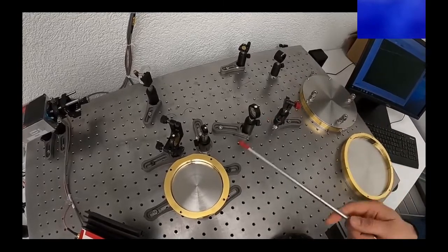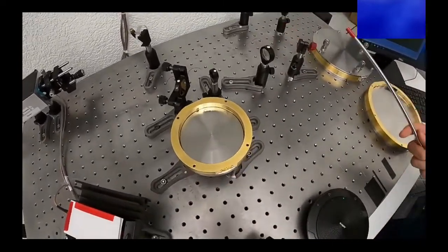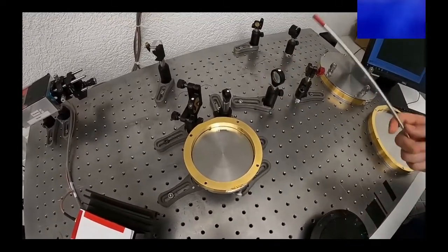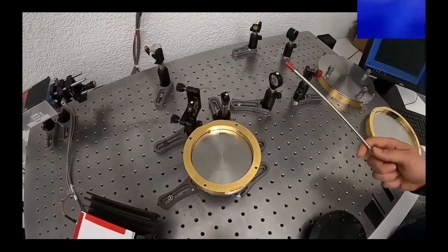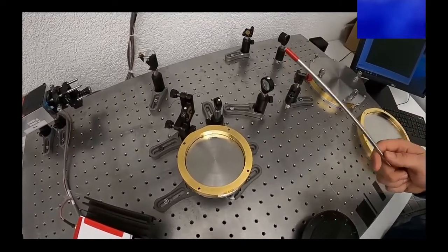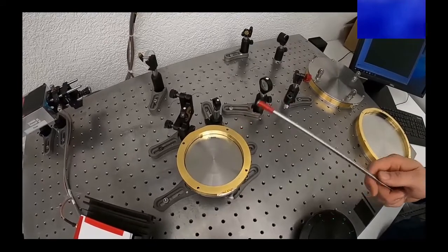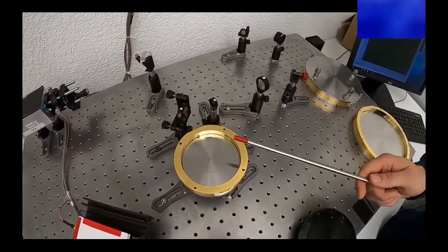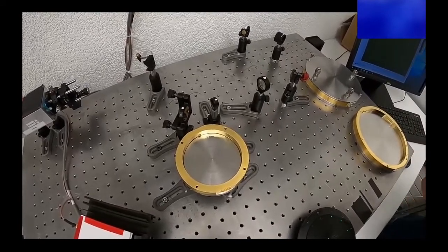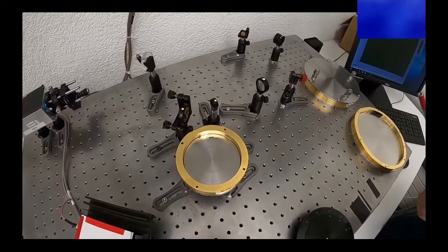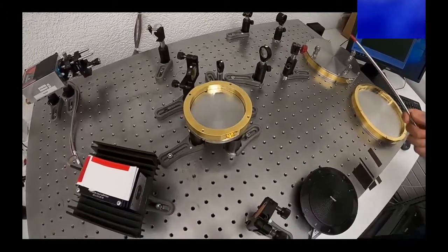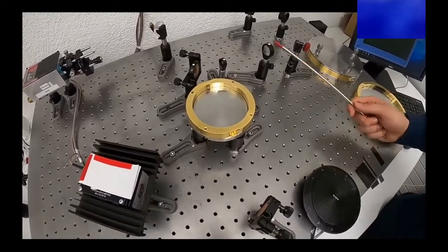After that, we have two lenses which make a telescope. In our case, we reduce the size of the beam roughly three times, and this is quite important to have low optical fringes. It is important to have the beam size or beam spot smaller than the dimensions of the mirrors in the cell, and the dimensions are 5 by 5 millimeters. So we recommend to have the beam spot definitely below 5 millimeters, best is to have somewhere between 2 and 4 millimeters. In this case, we go in with a collimated beam. It is also possible to couple into the cell with a focused beam.